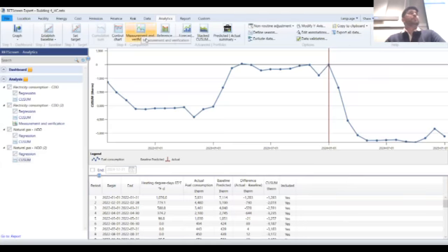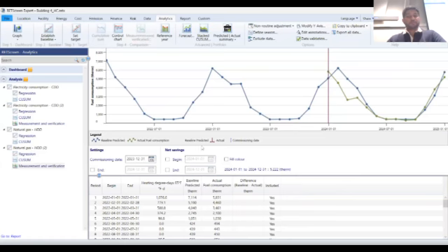You click on measurement and verification. Now I want to know how much therms I've saved. 5,220. This is with both window replacement and boiler upgrade, which ended almost simultaneously by the end of 2023. I want a whole calendar year. By default, it has calendar year data, or I want an annual year. It has 2024 and the savings end in December 2024. I can fill it by color, and I have 5,222 therms.